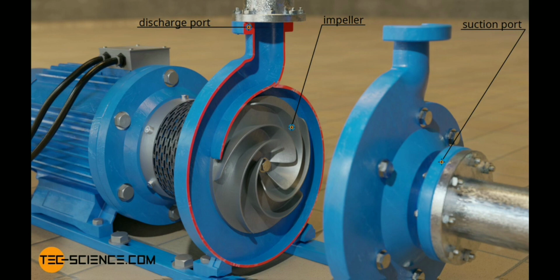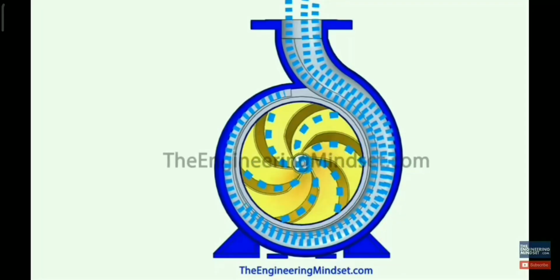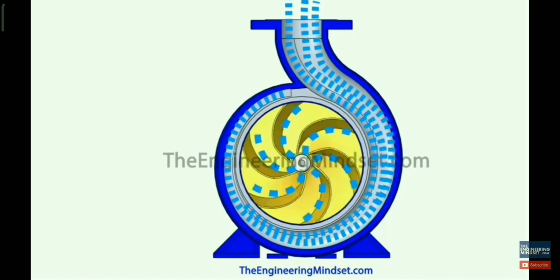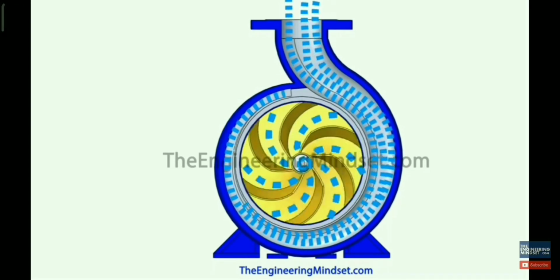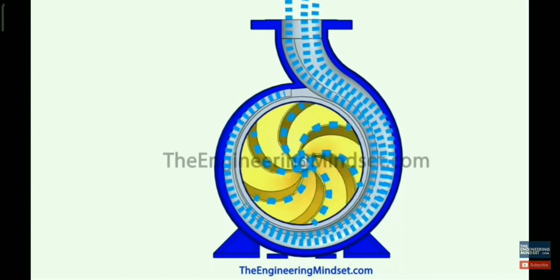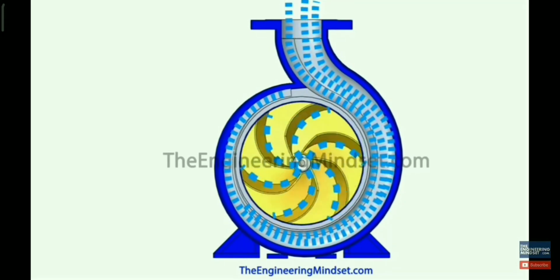First, through the motor, the suction is connected to the impeller, where the suction fluid goes to the center of the impeller. Through the spinning, the water or fluid flows in between the vanes, which helps to provide a force called centrifugal force, which pushes the fluid to the outer part of the impeller, flowing in the direction of the pump casing. Basically, we use a backward curved impeller, which is the most common and most effective design for moving a fluid. Actually, when the fluid goes to the center of the impeller, the pressure will be less. Through spinning, the fluid moves to the vanes, which push or accelerate the fluid from the higher terminal to the lower terminal.